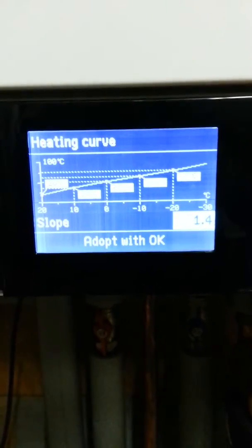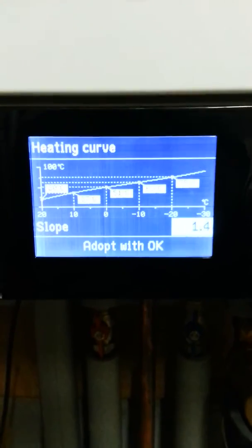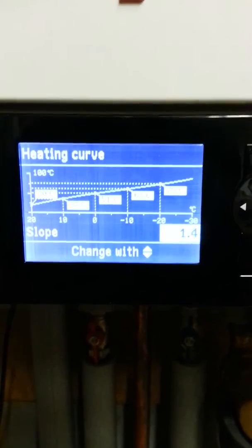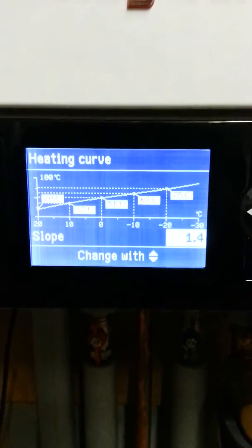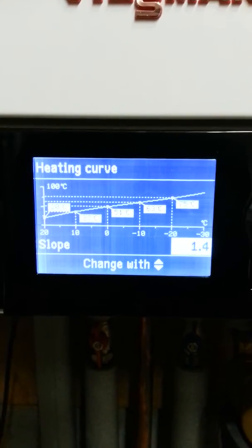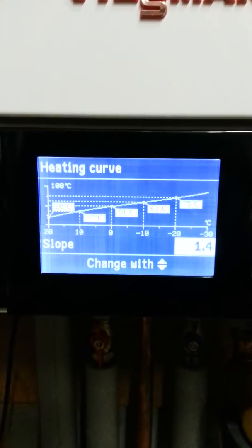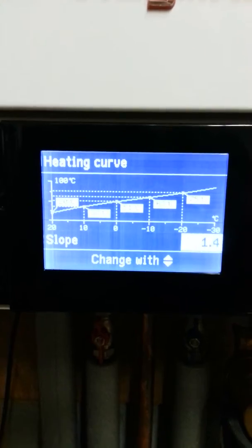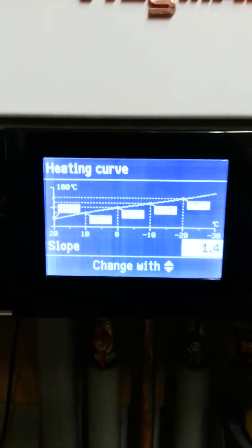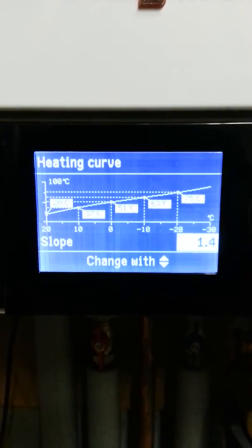This one is very typical. 1.4. Basically, exactly in line. It's how the boiler comes default. It's exactly in line with the outside temperature of minus three with a flow temperature of 54 degrees at minus three.